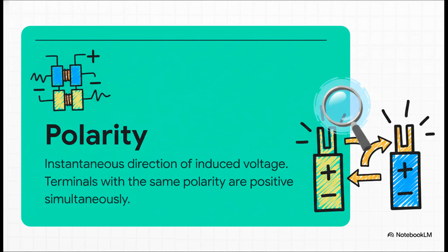So what is polarity? With AC power, voltage flips back and forth constantly. Polarity labels the plus and minus ends of the windings at a single frozen moment. For a parallel connection to work, you have to connect the terminals that hit plus at the exact same instant—they have to be in sync. The polarity test tells you which terminals are which.